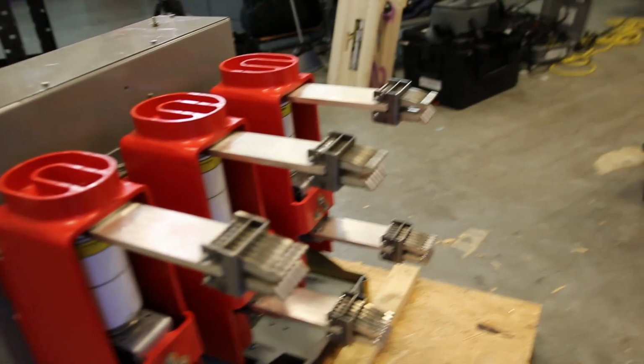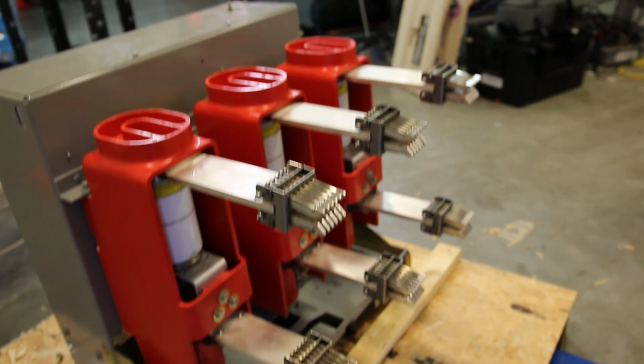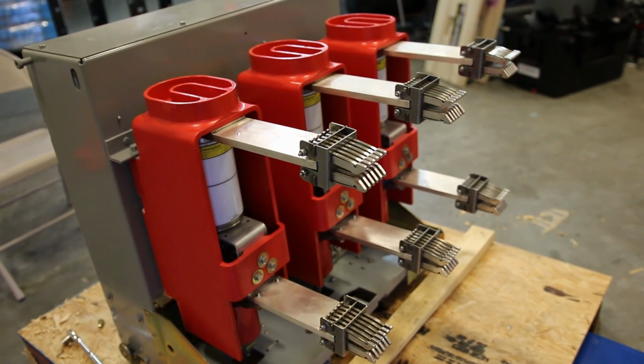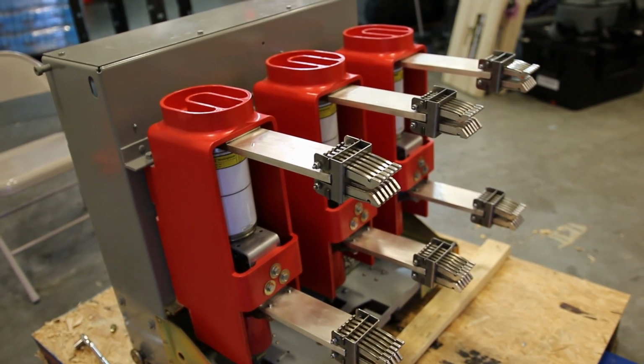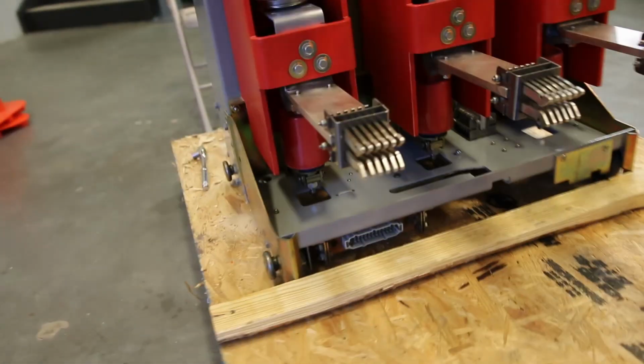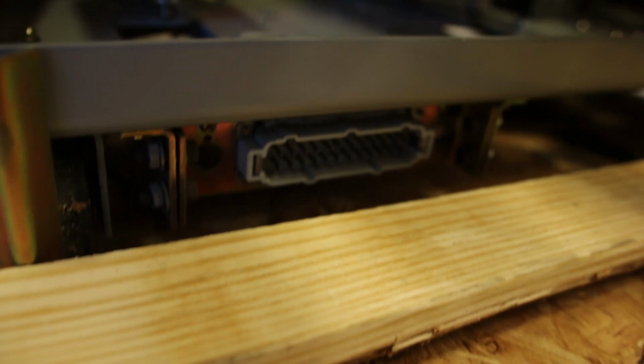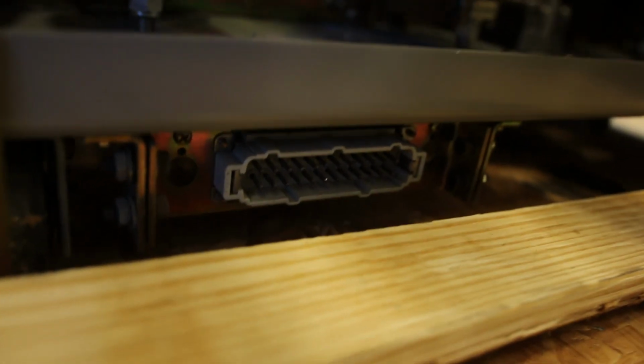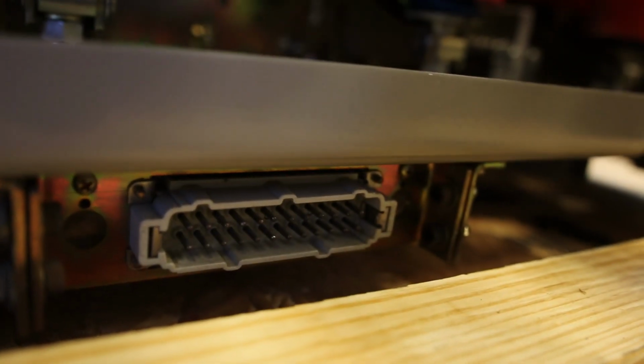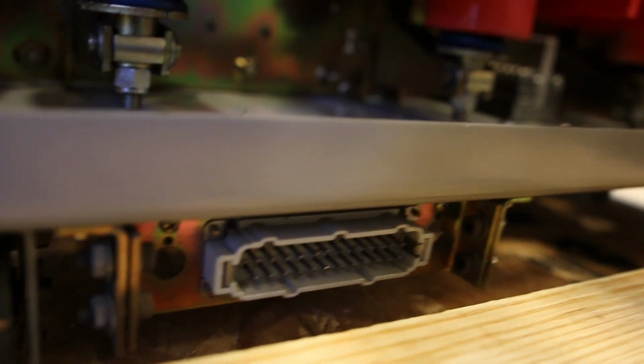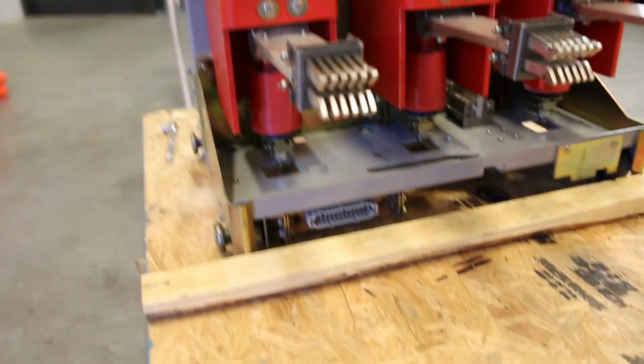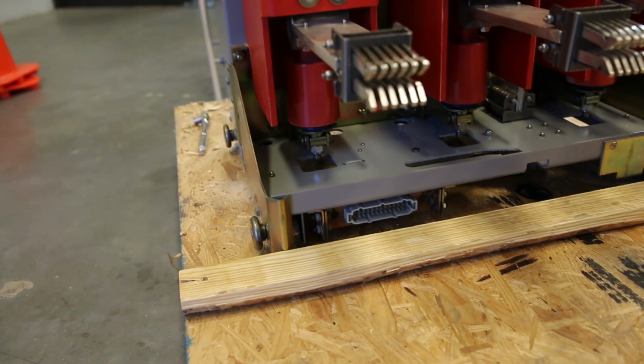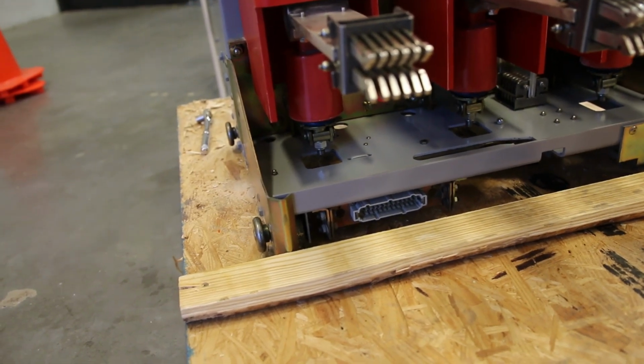These are the primary disconnects. That is when you rack the breaker into the cell. That's how the cell mates with the breaker, or rather the breaker mates with the cell. And these down here are our secondary disconnect pins. So that is how control signals and status signals out of the breaker are sent back to the control stuff in the cell.